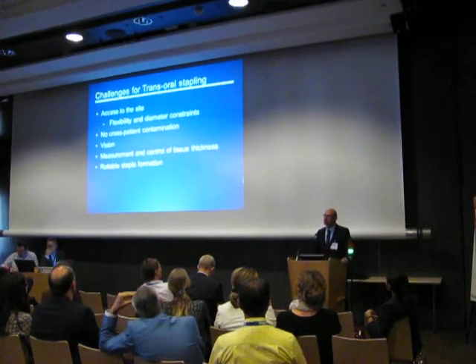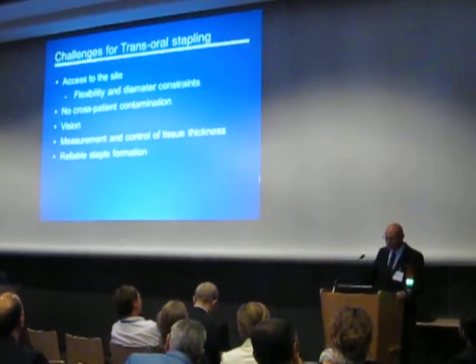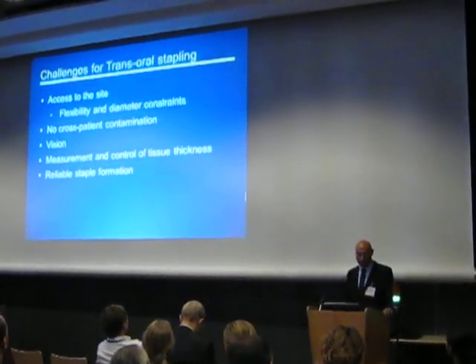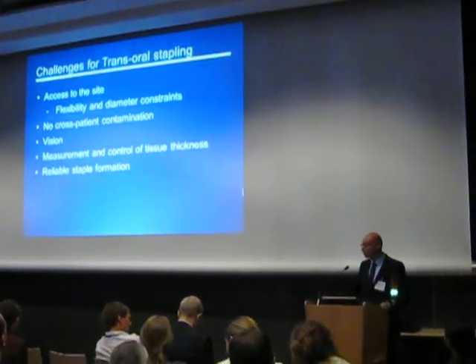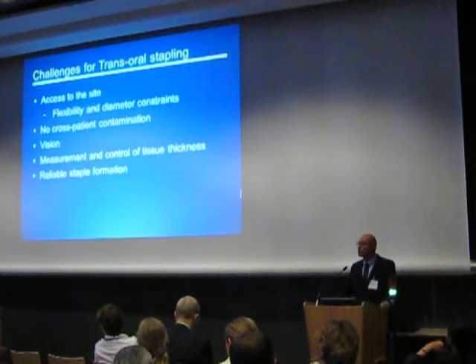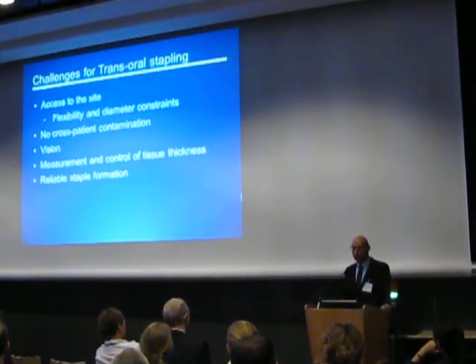When you build a trans-oral stapling device, there are a few challenges raised during the design. First of all, it should be flexible. Then it should be small enough to be introduced into the patient. We need to take care about cross-contamination with patients. Endoscopic vision is required. And stapling tissue requires that tissue thickness is measured at a certain point to make sure that the tissue is fully closed.